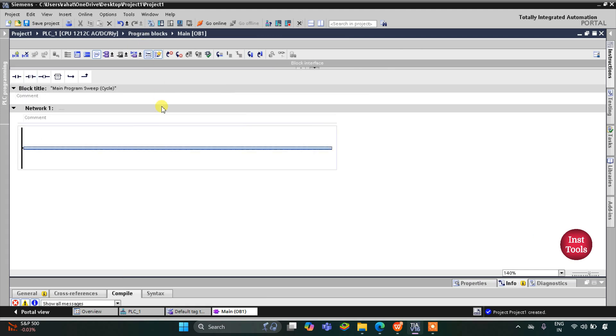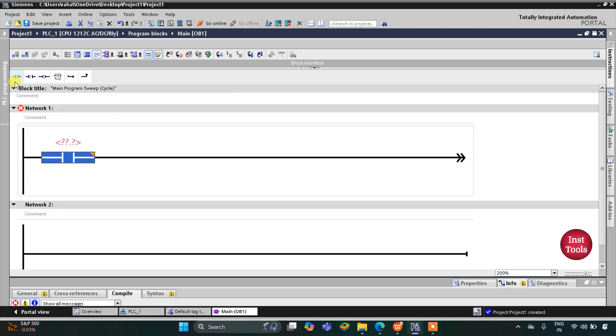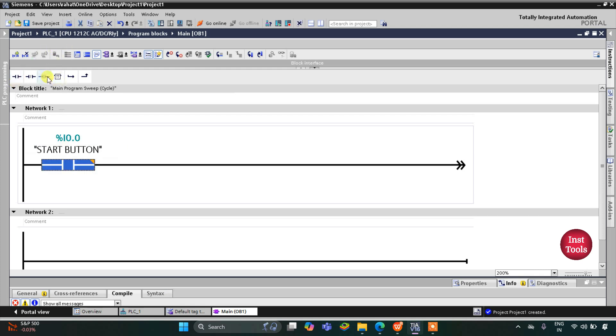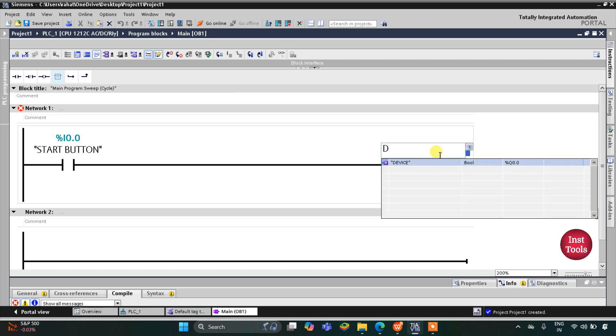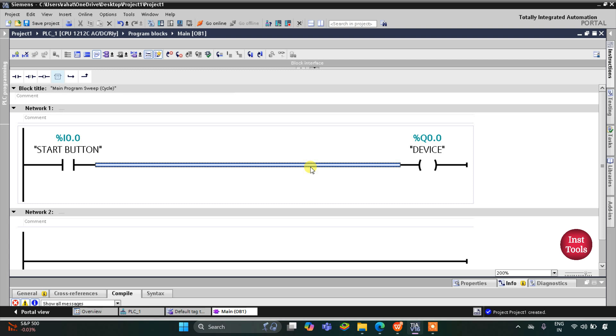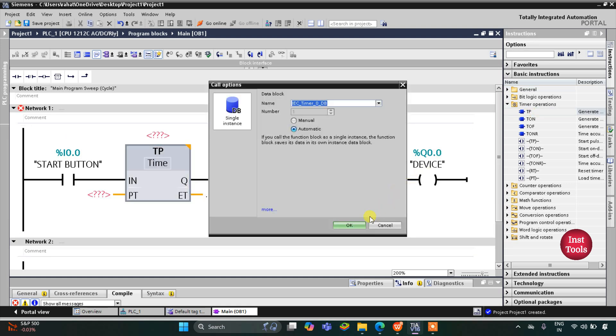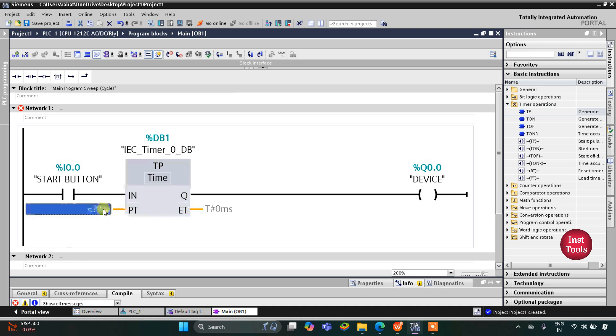Here we will draw the ladder diagram. I will insert a normally open contact for the start button — I'll write ST and select start button from the list. Then I will insert a coil for the device — I'll write T and select device from the list. Since the device should remain on for two seconds, I will add a timer. Go to timer operations and double-click on TP, then click OK.